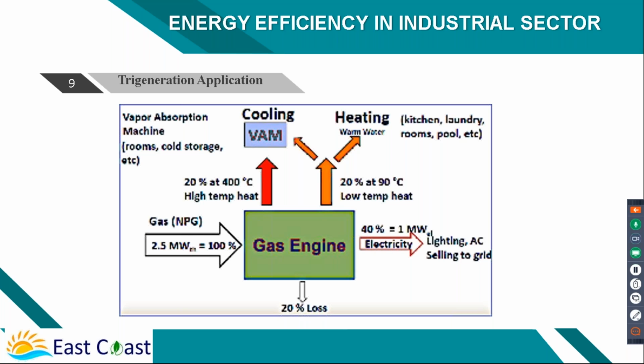That can be used - you can put a VAM there, you can put a small steam generator there, or you can put a small heat exchanger to produce hot water there, up to your choice. Similarly, another 20% comes out as jacket cooling water at around 85, 90 degrees. Even that water you can use to run a VAM and produce chilling.